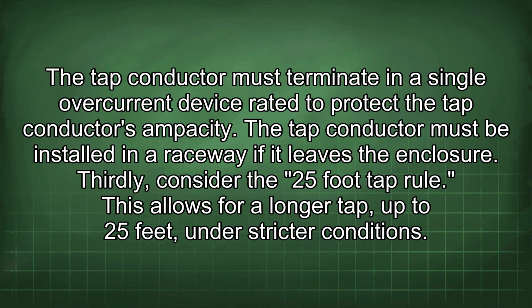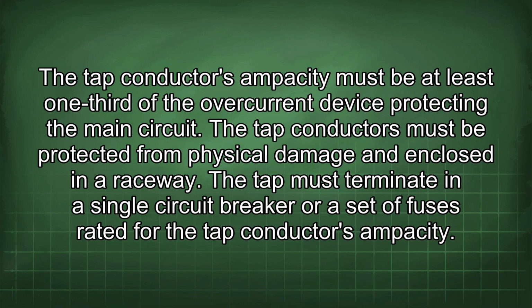Thirdly, consider the 25-foot tap rule. This allows for a longer tap up to 25 feet under stricter conditions. The tap conductor's ampacity must be at least 1/3 of the overcurrent device protecting the main circuit. The tap conductors must be protected from physical damage and enclosed in a raceway. The tap must terminate in a single circuit breaker or a set of fuses rated for the tap conductor's ampacity.